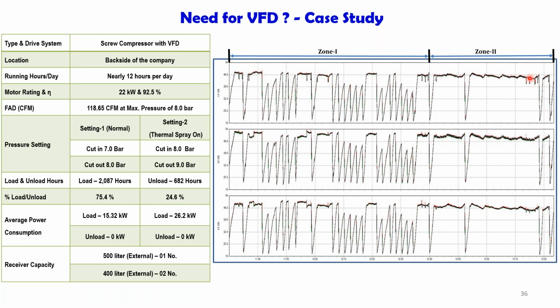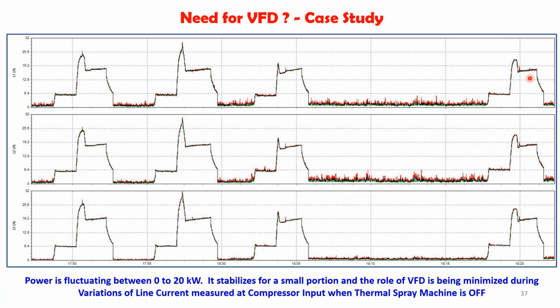So we found out why this is happening. Similarly, when the thermal spray machine is off, we took a recording and found that the compressor itself has a setting: when the air is not used by the company for the product application, it goes to standby mode. The motor will be turned off. So this is the profile we got. So we had some doubt whether the VFD is required for this application or not, because the motor itself is turned off when the air is not used in the system. Then what is the need for the VFD in this case?